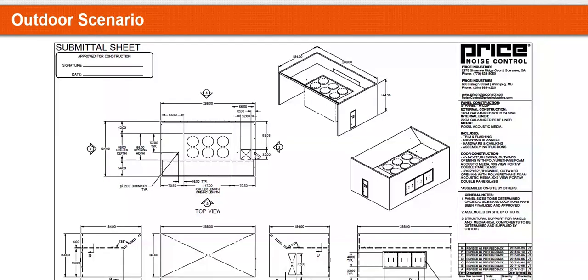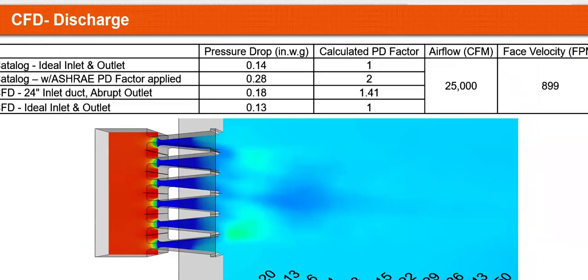So here you have an example of the submittal, and you'll see that we have very large openings and no openings on the sections or on the paths where you have a direct line of sight, allowing for access for the coil. So these access doors at the back would line up specifically with the V coil so that they could remove them without having to take the entire enclosure apart, along with a fully removable silencer bank at the top. In case they need to replace that chiller, then they can take the lid off, put the new chiller in without having to size a new enclosure.